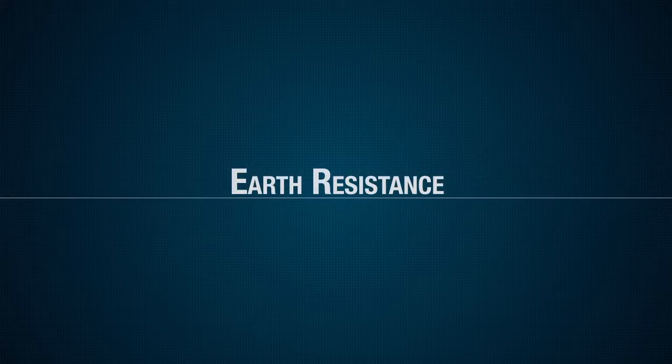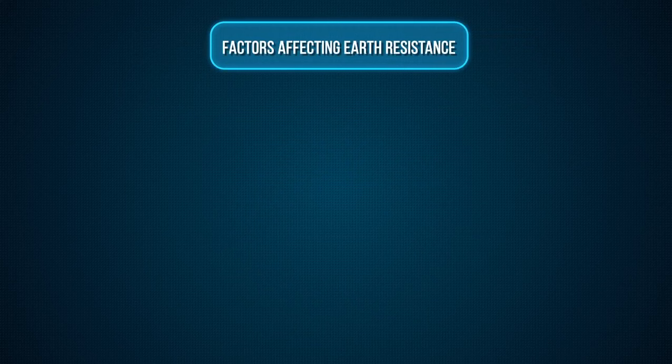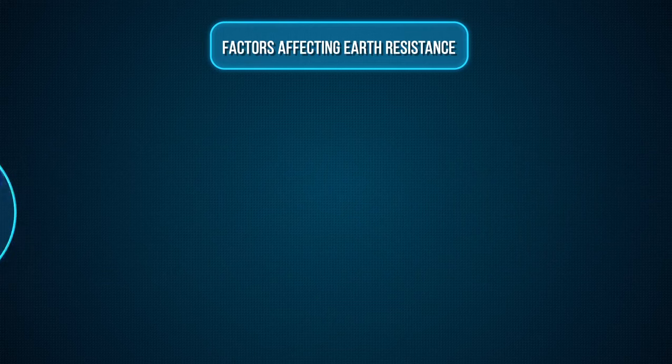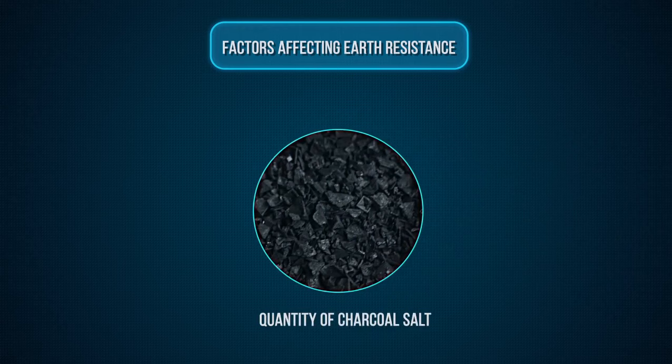Earth resistance. The resistance offered by the earth to the flow of current is known as earth resistance. The earth resistance is affected by the following factors: material properties of the earth wire and earth electrode, temperature inside earth pit, moisture content of the soil in earth pit, depth of the earth pit, and quantity of the charcoal salt layer used inside earth pit.